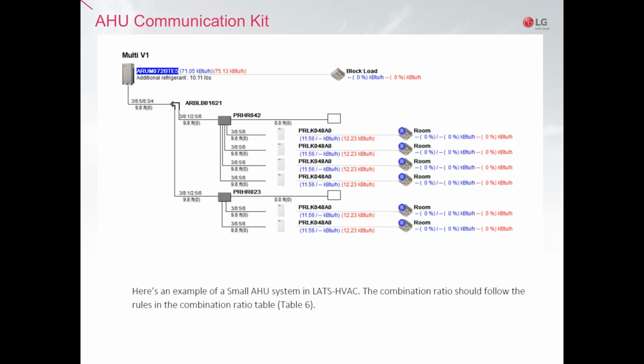Coming out of that line, we branched the pipe system in two and connected each side of the Y branch into a heat recovery port. One of the boxes is 4-port, the one on top, and the one at the bottom is only 2-port. As a note, the sizes we have for these boxes are 2, 4, 6, and 8 ports. Each of the ports is connected to a single EV kit, and all of them are noted as PRLK048.